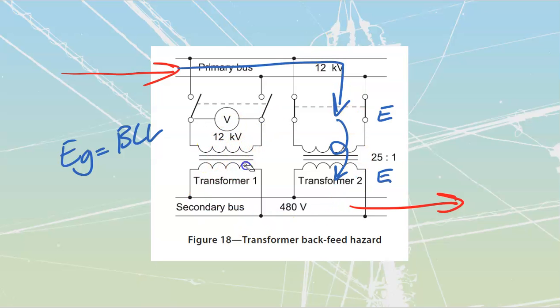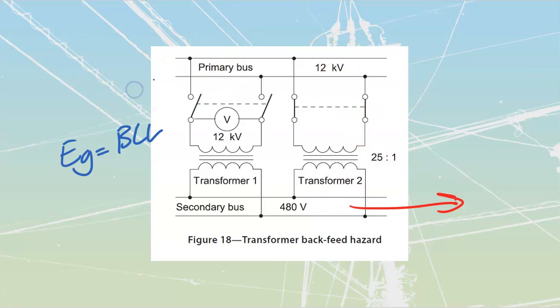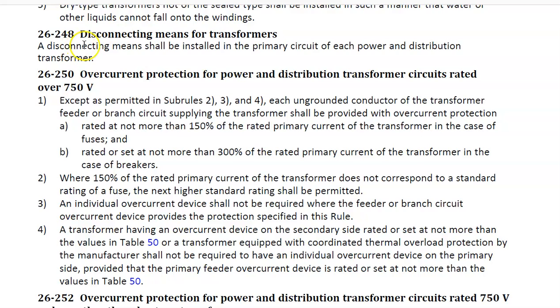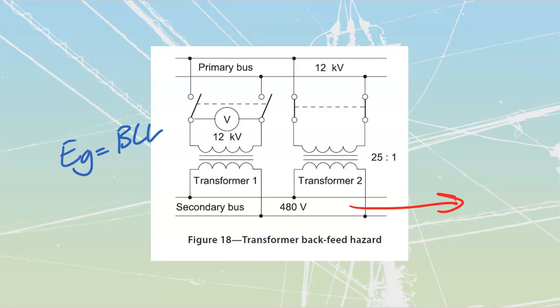Now, the Canadian Electrical Code only has requirements that we place a disconnect. That same rule that we were just looking at there, 26-248, says that we have to have a disconnecting means in the primary of our circuit. It says nothing about needing to have one inside of the secondary.